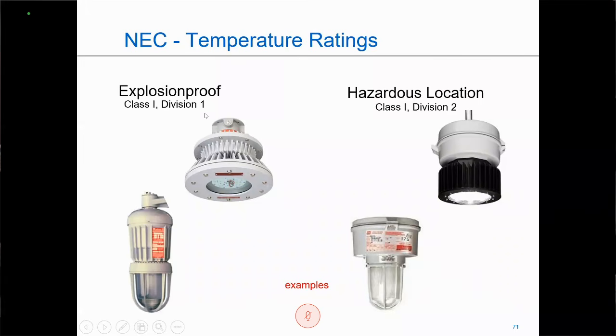This fixture will contain an explosion. So when I have my temperature ratings, I'm taking it on the hottest point externally, because this particular unit, if the gas were to get inside, will contain the explosion. So I really don't, for lack of better words, care if the gas gets inside. Now, I'm not trying to trivialize gas migrating in, but in a Division 1, we assume that's happening. So if something inside the fixture is too hot, that fixture is going to contain the explosion, cool the gases, and harmlessly release them back out to the atmosphere. Now, my Division 2 fixture, here I'm taking my temperature rating on the hottest point internally.